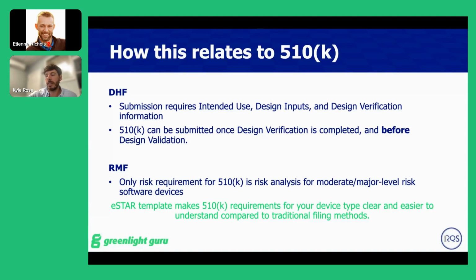So you can't submit a 510K or PMA until the device has been formally tested and those test reports are ready for the FDA. So at a high level, your 510K or PMA typically covers your design inputs at a very high level, but mainly your design outputs and your design verification activity. It'll also have your intended use, your labeling and packaging of your device.